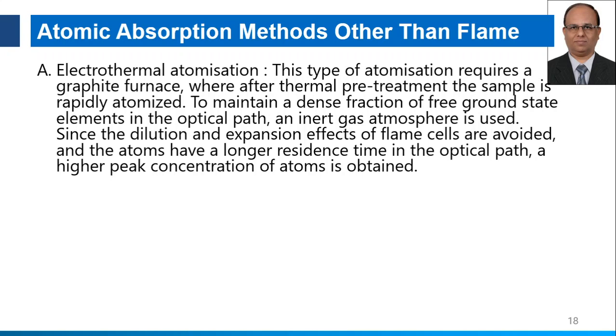Atomic absorption methods other than flame — flameless techniques — can overcome certain disadvantages of flame techniques. The first is electrothermal atomization, which requires a graphite furnace. After thermal pretreatment, the sample is rapidly atomized; an inert gas atmosphere is used to maintain a dense fraction of free ground state elements in the optical path. Since dilution effects of flame are avoided and the atom has a longer residence time in the optical path, a higher peak concentration of the atom is obtained — giving more intense peaks with the electrothermal atomization technique.